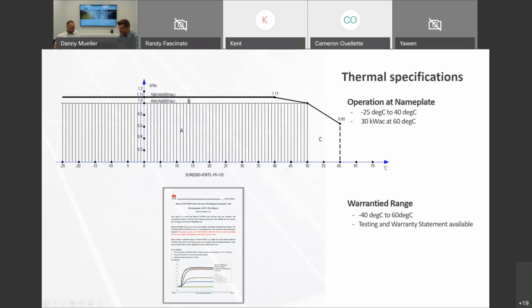The Huawei inverter at the 50 kilowatt level can produce full nameplate output power up to 40 degrees Celsius. And the regular data sheet goes down to minus 25 degrees C for full power operation. Since we are in Canada and we typically experience harsher weather conditions and climate conditions than our neighbors in the south, Huawei has a special testing document available, which also refers to specific warranty conditions. And Huawei, for the Canadian market, warranties the unit all the way down from minus 40 degrees C up to 60 degrees C. And of course, at 60 degrees C ambient temperature, which is unlikely to occur in the Canadian climate, the power will then be curtailed. So everything above 40 degrees C will have some curtailments in power.